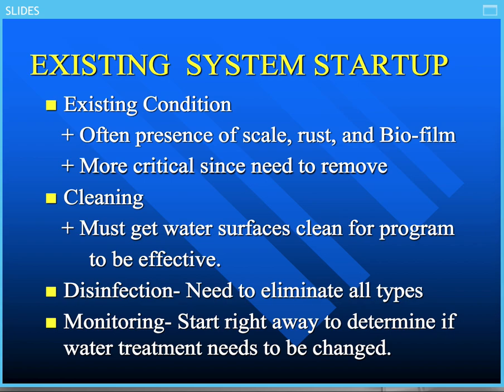Does it need more biological control, more corrosion control, more scale control? All of these things are necessary to look at to determine what's going on. But you've got to monitor right away from the start. Now, I should mention monitoring can be done several ways. One, of course, is to look at heat transfer and what you're getting on heat transfer. The other aspect is how you can determine what the corrosion rate is.